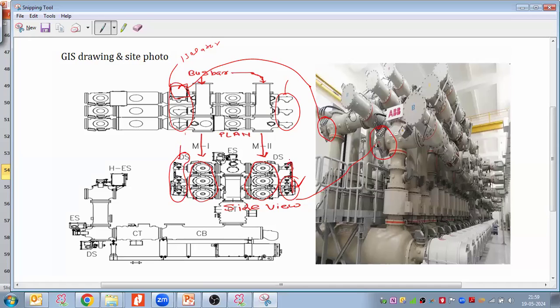The disconnector is preferably arranged side by side with the bus bar. So this represents the disconnectors. And this portion represents the earthing switch, the bus bar earthing switch that we take between two disconnectors. On the top of the modules here, we are taking the maintenance earthing switch.